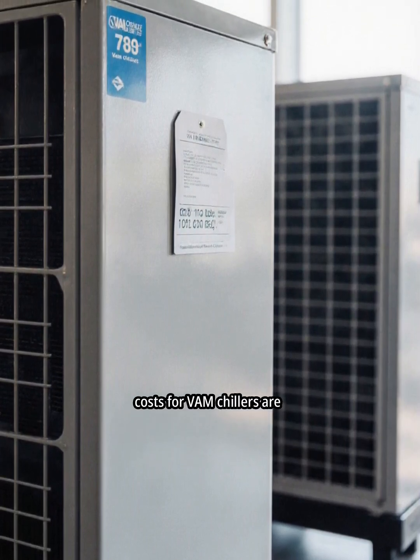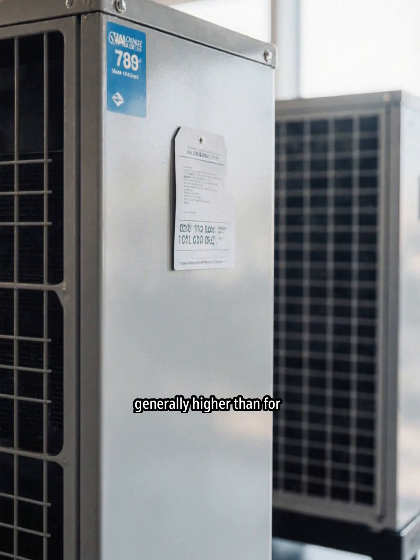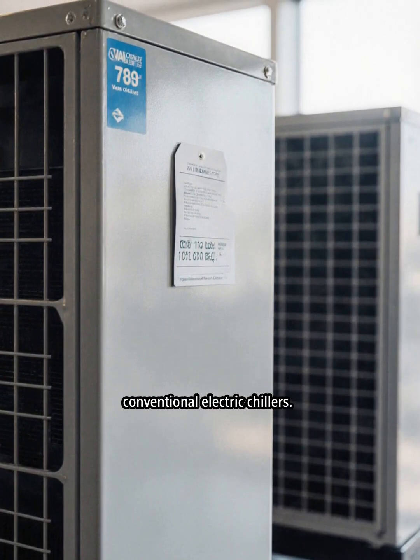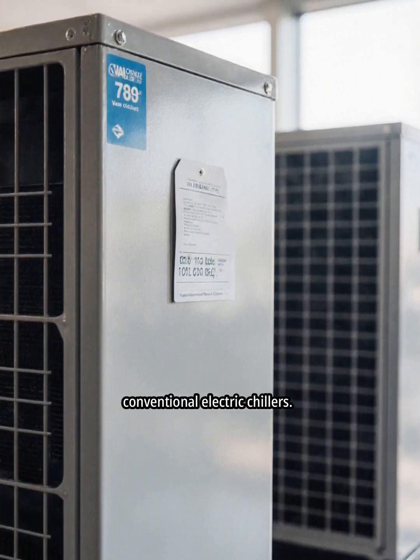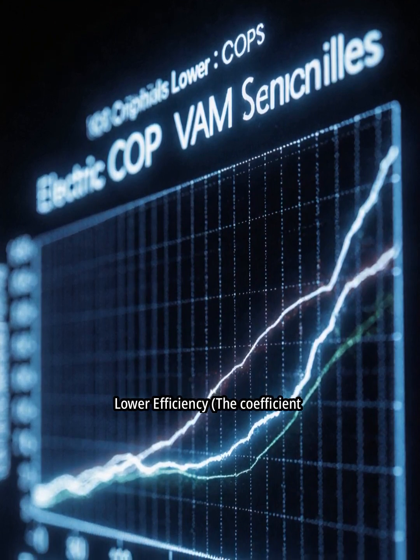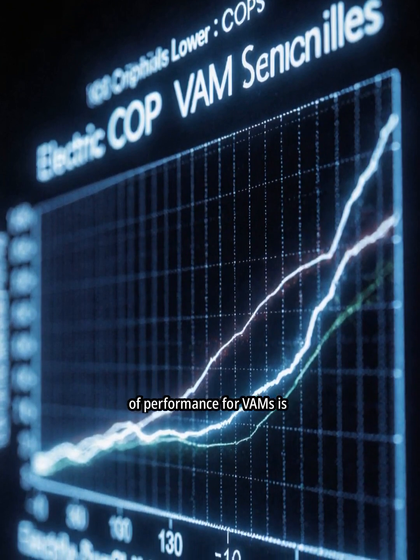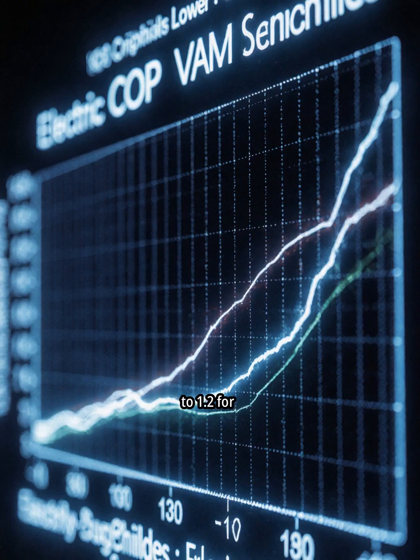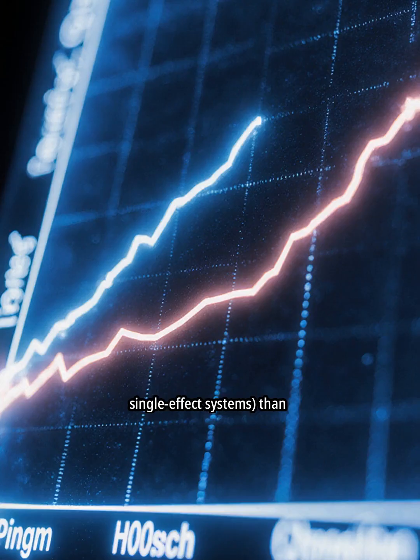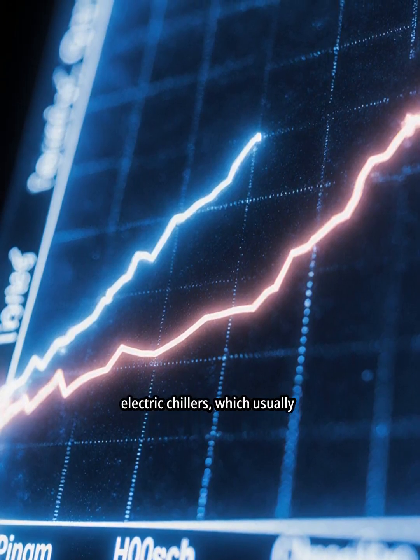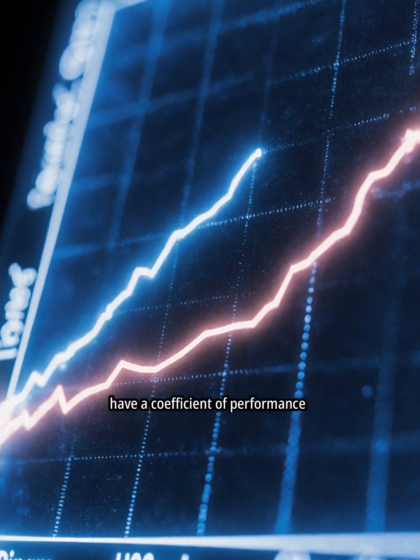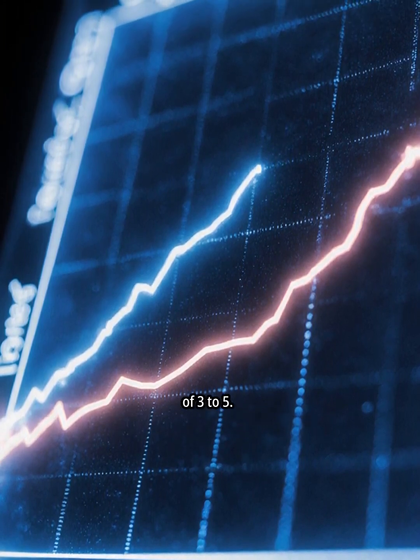The upfront investment and installation costs for VAM chillers are generally higher than for conventional electric chillers. Lower efficiency. The coefficient of performance for VAMs is typically lower, around 0.6 to 1.2 for single-effect systems, than electric chillers, which usually have a coefficient of performance of 3 to 5.